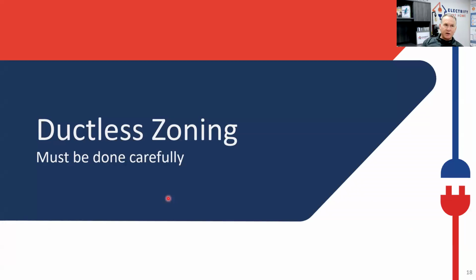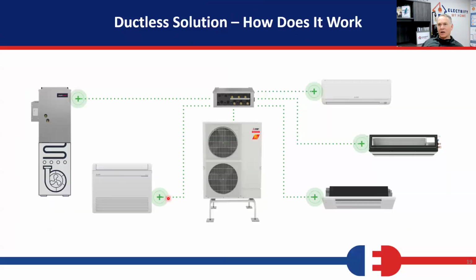Ductless zoning must be done very carefully as well. What I'm talking about is multi-zone mini split systems, which are very particular, and there's an issue that exists with these. These are pretty good with the zone boxes or the branch boxes. They're going to be potentially a little better, but we're setting ourselves up for a lot of problems, because we don't want to just think about the true comfort that's been brought to us through the system. We also want to think about the cost to the customer.